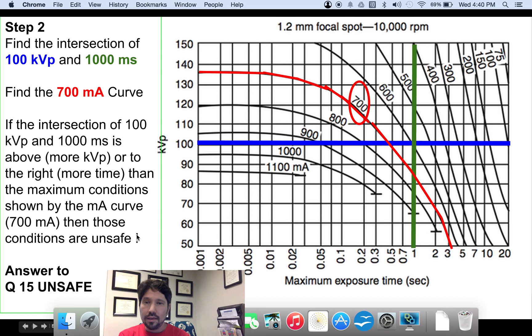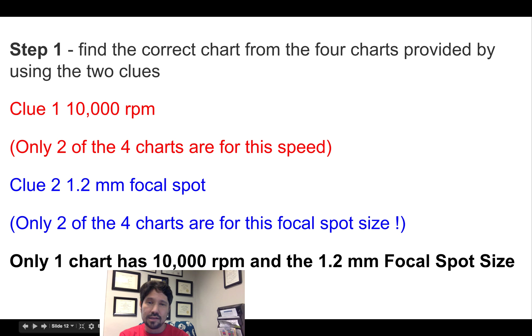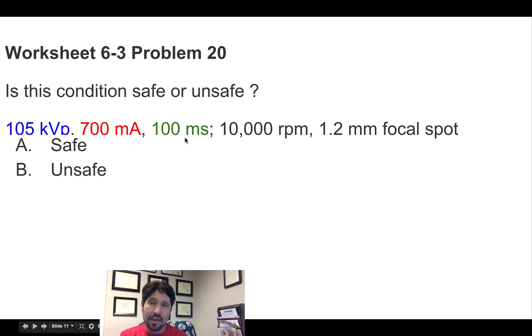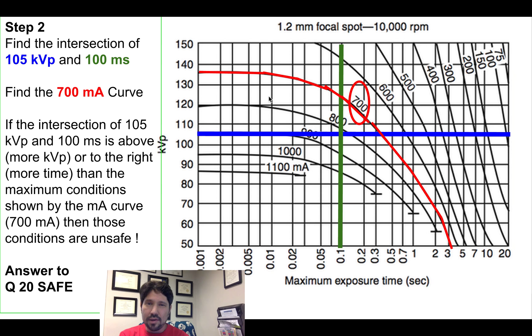Alright, we'll do one more. Again, it's the same RPM and the same focal spot. So we'll grab the same curve. And now we've got 105 kVp, 700 mA for 100 milliseconds. So we grab that same curve. We set up 105 kVp as my blue line. 0.1 second is 100 milliseconds. And that is below, it's to the left of the curve. It's below the curve. So at 0.1 seconds, I can go all the way to almost 125 kVp. Or at 105 kVp, I could go almost to 0.35 seconds. But as long as I don't go to the right of the curve, more time or above the curve, more kVp, I'm safe. So for this answer, I would be safe.